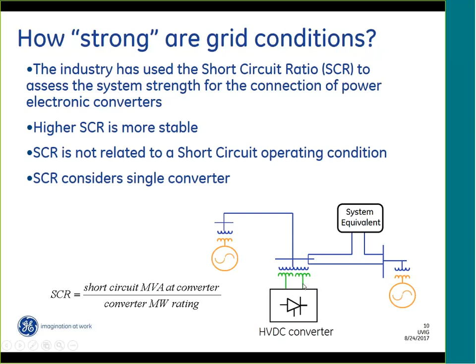A few comments related to this. The name short circuit ratio tends to be confusing because although it's a short circuit ratio, we're not really trying to understand a short circuit operating condition. We're basically trying to understand how strong the system is, like what is the impedance seen from the converter I'm connecting. So we shouldn't get confused with the name. This is not related to a short circuit operating condition. We may use a short circuit tool to calculate it, but this is not related to a short circuit operation. And then a very important characteristic of this index is that it considers a single inverter. So in this equation, I basically have a single location of a converter and I calculate the short circuit MVA at that location. So let's see how this applies to wind plants.